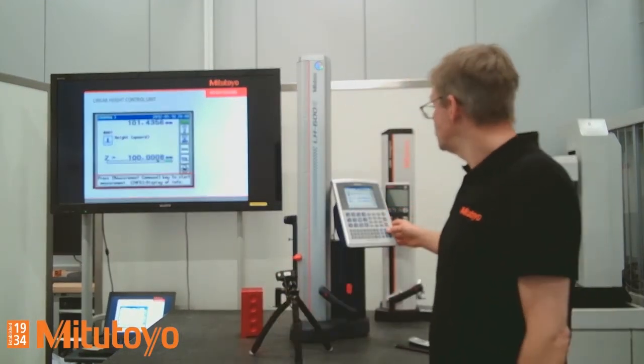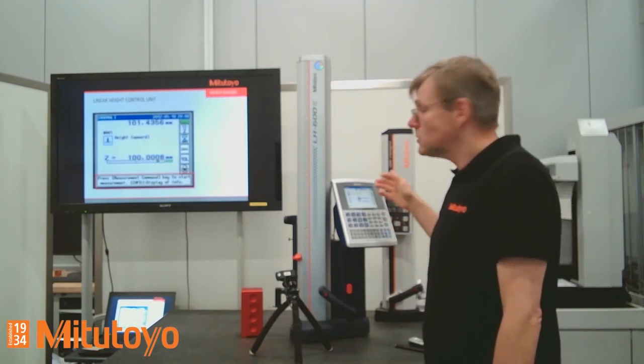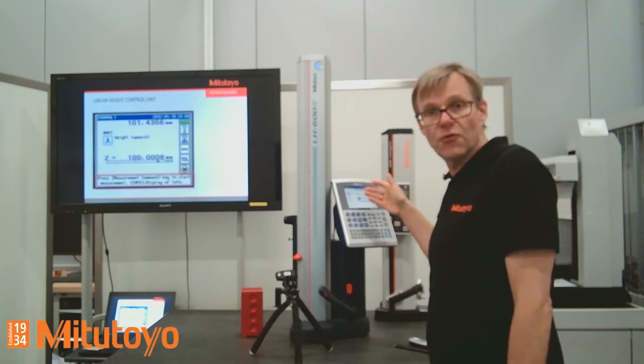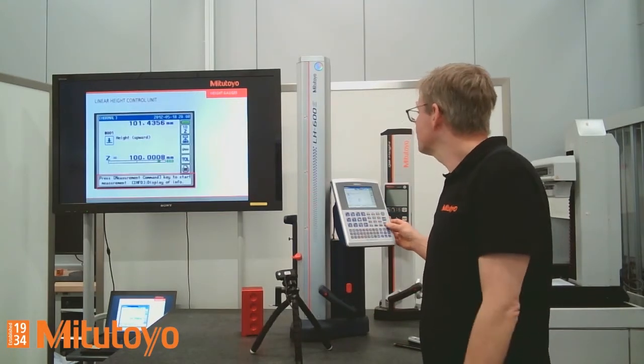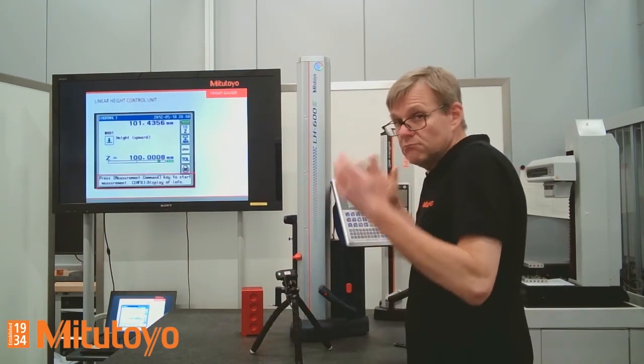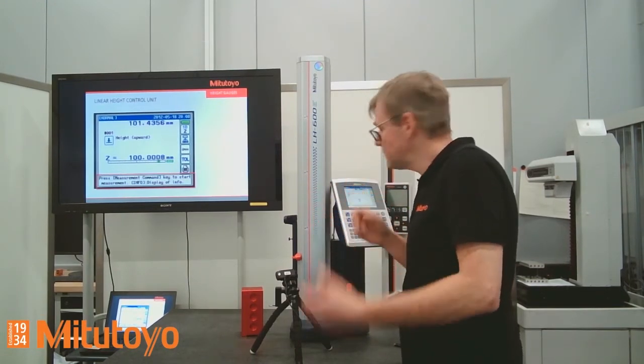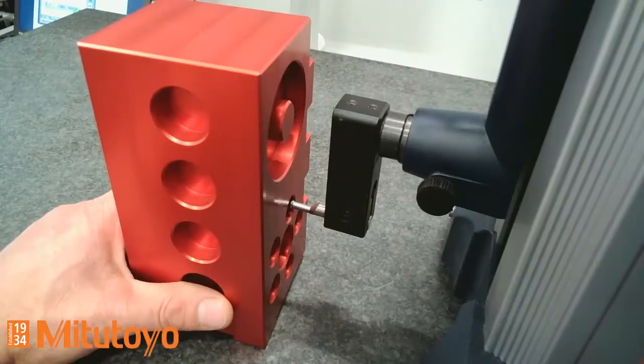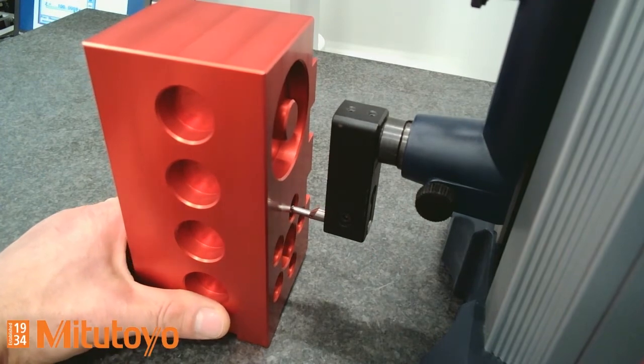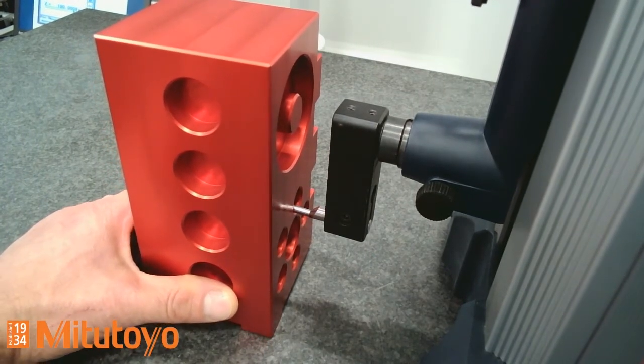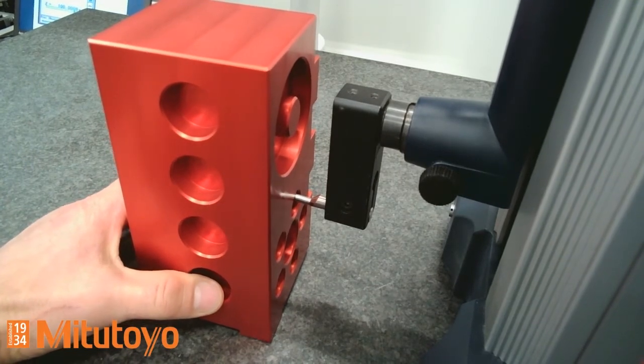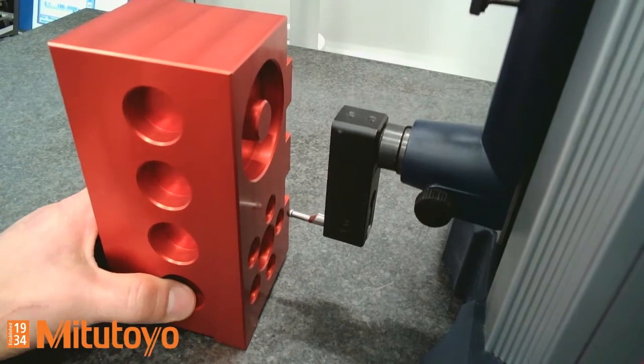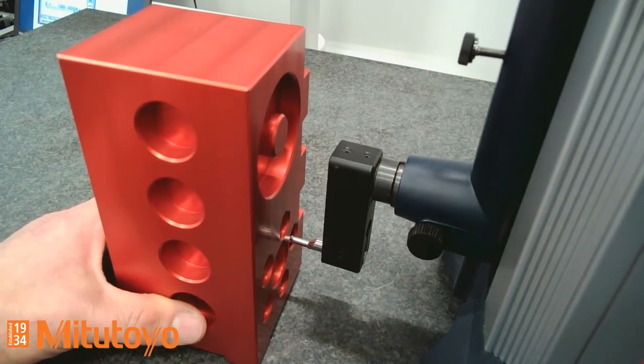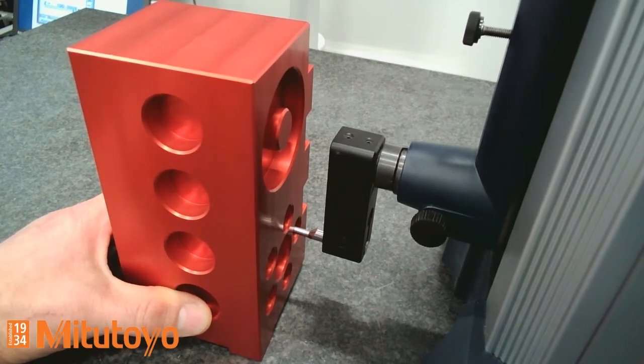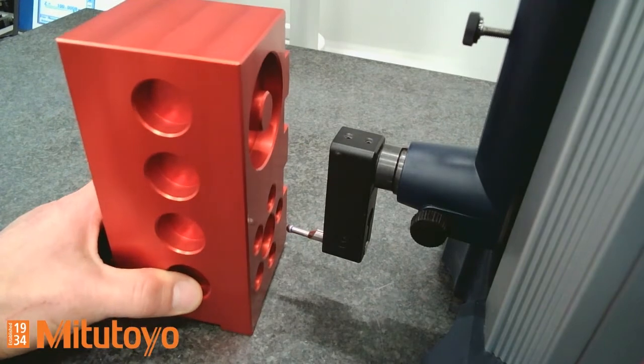Okay, I switch to two-dimensional mode. And the controller box is asking, please measure first of all Z component. Okay. I will use the circles. Maybe three circles is a minimum for a pitch circle diameter. Let's do the measurement of three circles. Next one. And the last one.